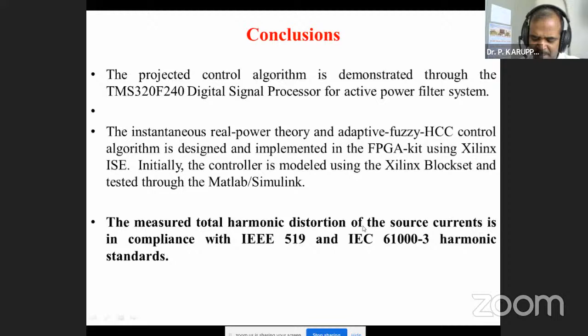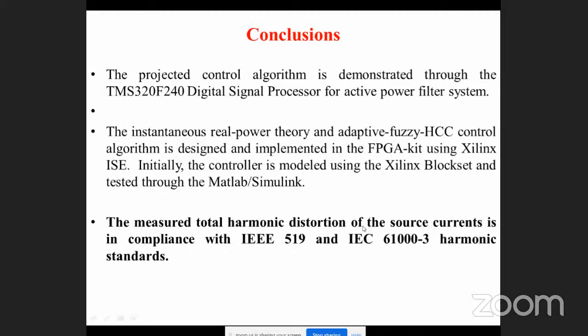So the total harmonic distortion of the source current is compliant with the IEEE 519 and IEC 61000-3 harmonic standards. As per the harmonic standard, the acceptable current THD should be less than 5%. So this is demonstrated.